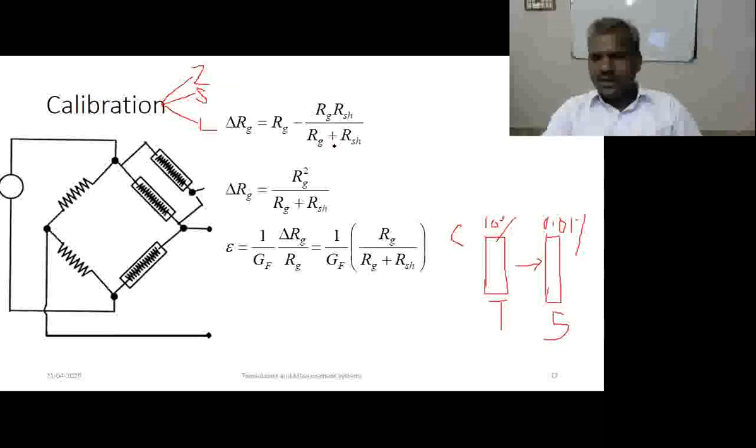First, give zero input from the standard. Check whether the instrument is showing 0 or not. Next, give the entire range, that is the full range of the instrument, which is called span, the maximum value. Then linearity. This linearity is nothing but the mid value check.